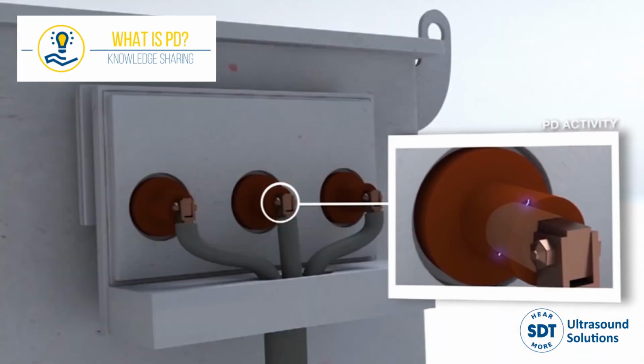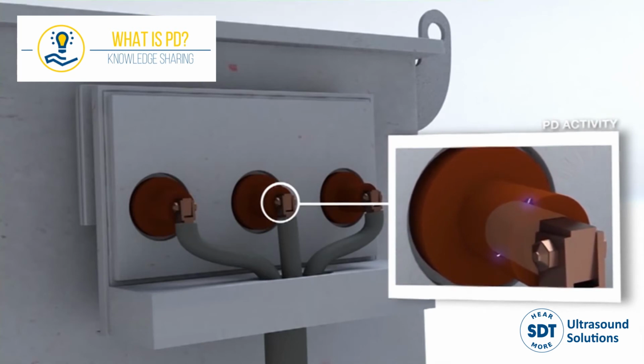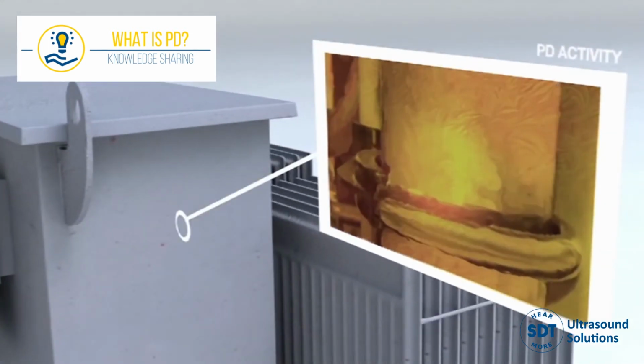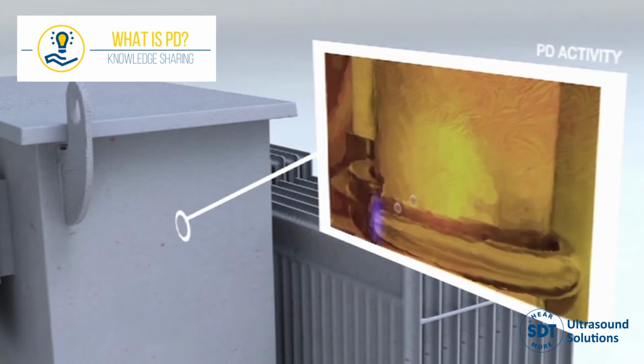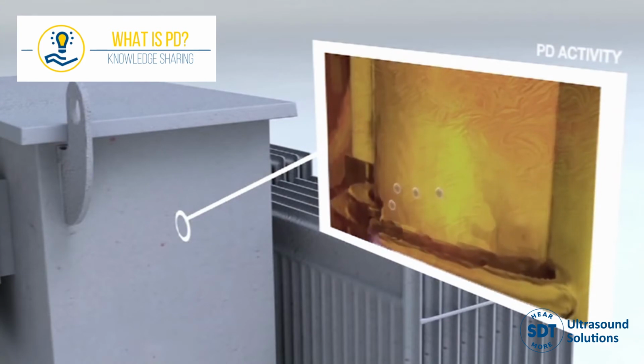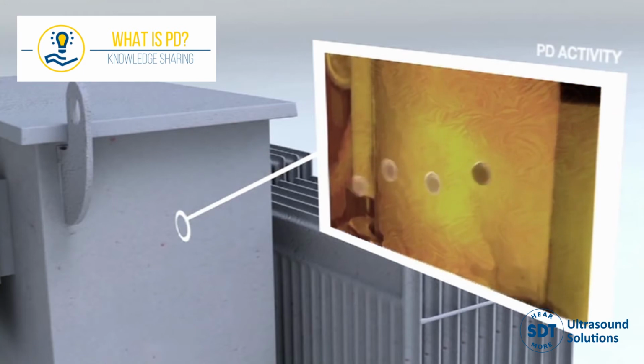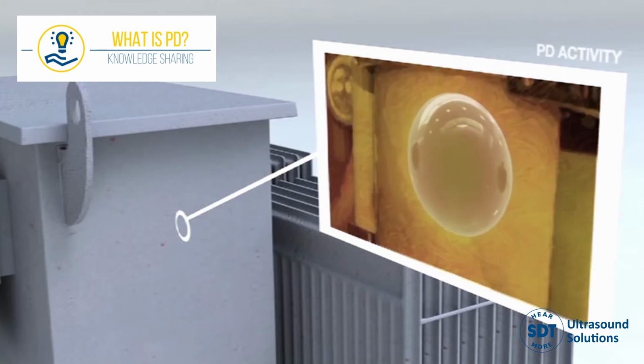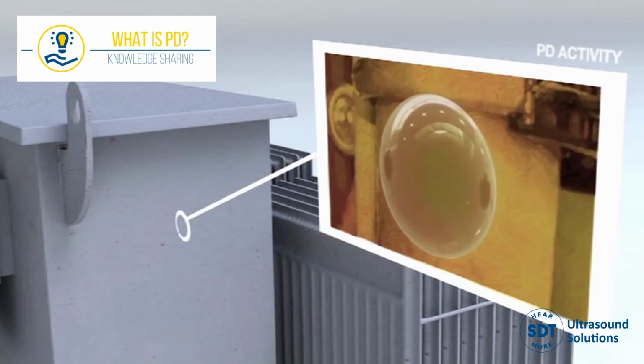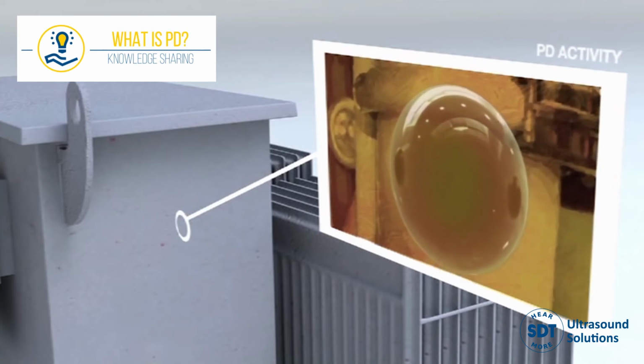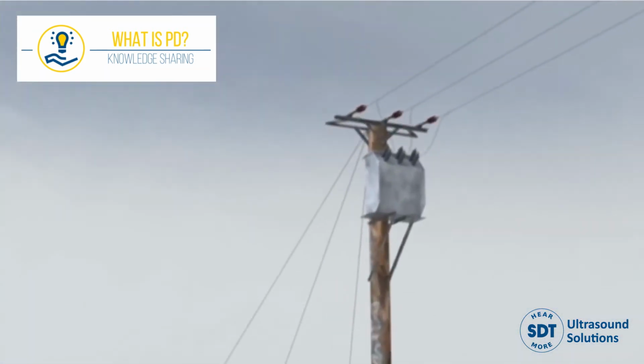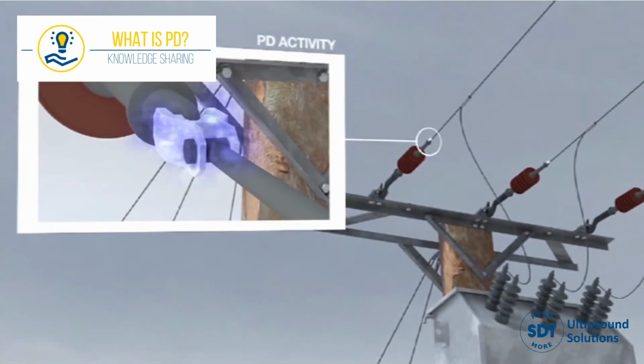This could be due to voids within a solid insulation material, across the surface of insulating material, in gas bubbles within liquid insulation, or around electrode edges in the form of corona. Partial discharge is an atomic reaction which, due to the movement of electrons, ionizes the air molecules at locations of high stress. Ionization splits the oxygen molecule to form ozone and nitrous oxide, which in their normal states are generally harmless, but when you mix them with water vapor, they become corrosive.